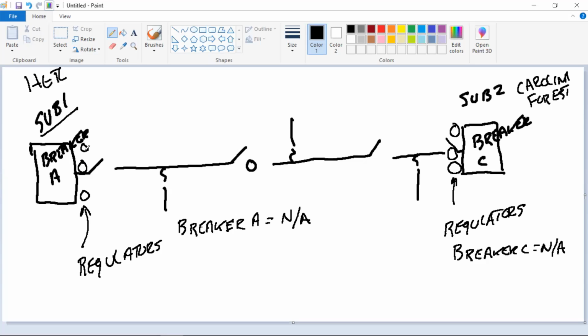In order for me to get both breaker A and breaker C at these substations to what they call tie together, and this goes back to the days that we talked about, the higher the voltage, the lower the what? Amperage. Amperage, right? And the lower the voltage, the higher the amperage. What you'll have to do is match the voltages between breaker A and breaker C. How can we match voltages at both substations? With the regulators. Right, the regulators at both substations have to be matched so they match each other. And it's down to a pretty precise within a volt range.